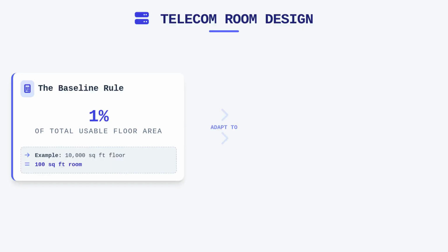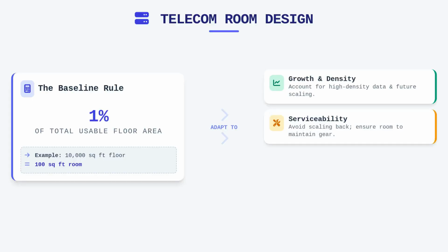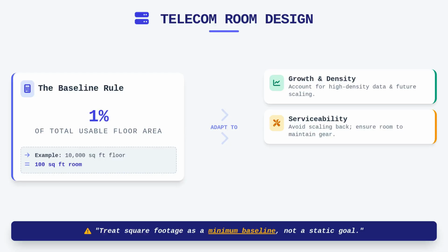For instance, if you are designing for a floor plate of 10,000 square feet, you should plan for a room size of approximately 100 square feet. However, simply adhering to this ratio is often insufficient if the facility has high-density data requirements or specialized cabling needs. You must treat this square footage as a minimum baseline rather than a static goal, as scaling back space often results in an inability to service the equipment properly later. Always verify that your dimensions accommodate the essential rack units, which are defined as 1 3/4 inches of vertical space, while also allowing for the necessary horizontal cable management footprints.